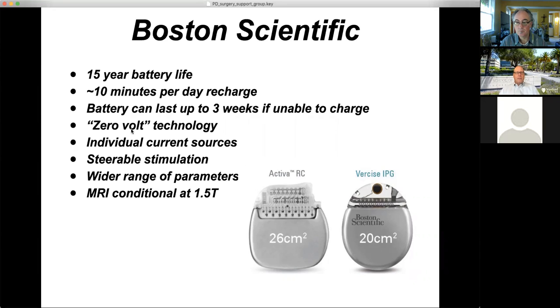An advantage of the Boston system, aside from this 15-year battery life, is there are individual current sources, which means that you have the ability to steer the stimulation around, which lets you reduce side effects, because sometimes if there's current spread to other areas, by steering the current away from that, you can reduce those side effects. There's a wider range of parameters, and you can get an MRI scan up to 1.5 Tesla.